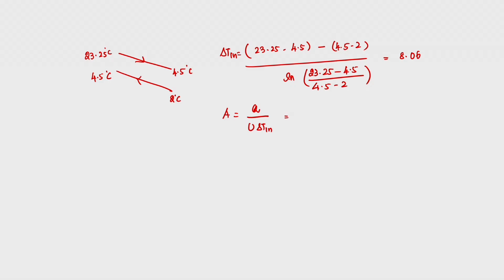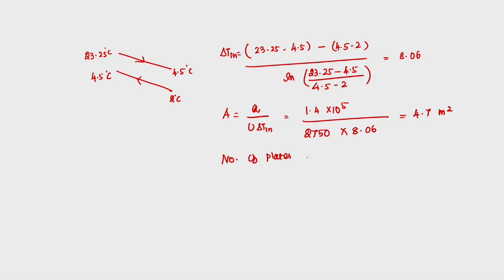So, area is Q upon U del T ln. Q we just calculated is 1.4 into 10 to the power of 5, divided by U, which is given as 2750, and the logarithmic mean temperature difference is 8.06. If you substitute, you will get around 4.7 meters squared. So, the number of plates required is 4.7 upon 0.79, which is around 6 plates.